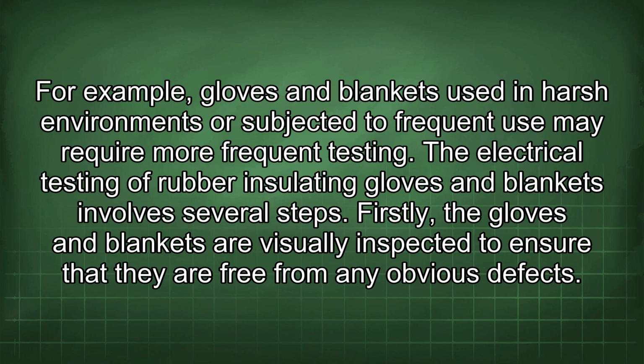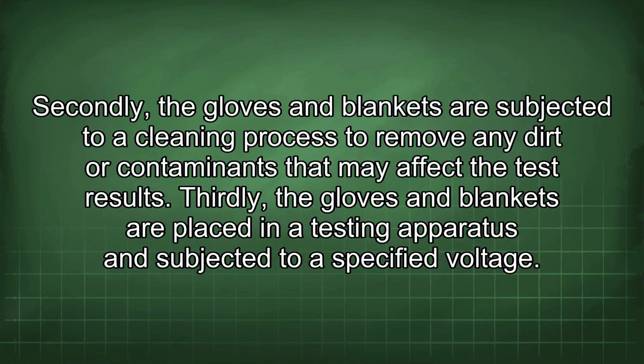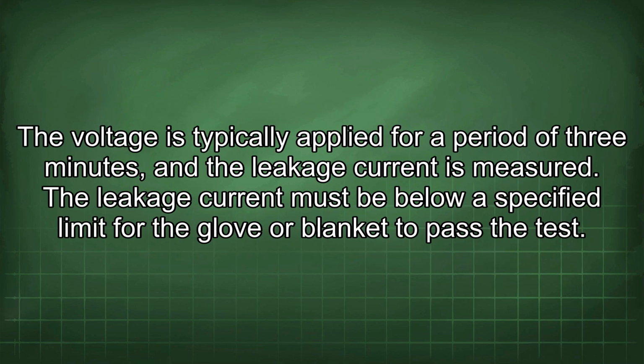The electrical testing of rubber insulating gloves and blankets involves several steps. Firstly, the gloves and blankets are visually inspected to ensure that they are free from any obvious defects. Secondly, they are subjected to a cleaning process to remove any dirt or contaminants that may affect the test results. Thirdly, they are placed in a testing apparatus and subjected to a specified voltage. The voltage is typically applied for a period of 3 minutes, and the leakage current is measured. The leakage current must be below a specified limit for the glove or blanket to pass the test.